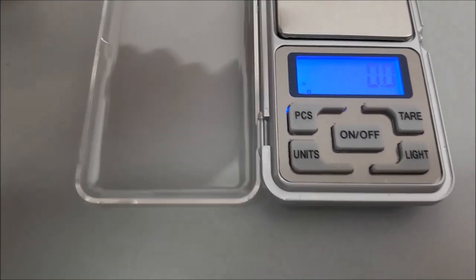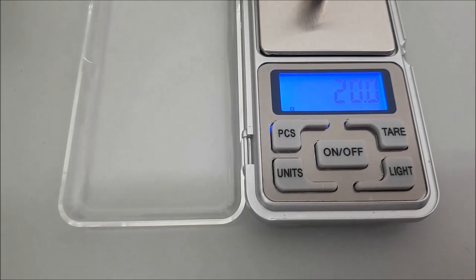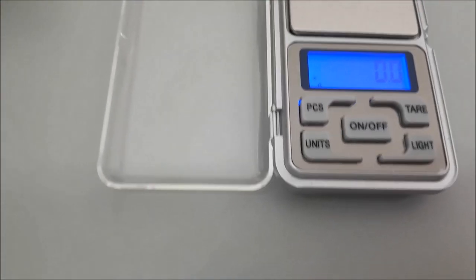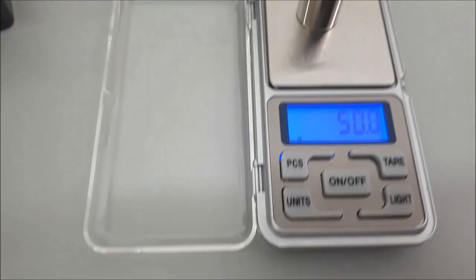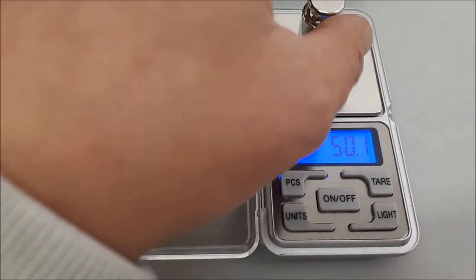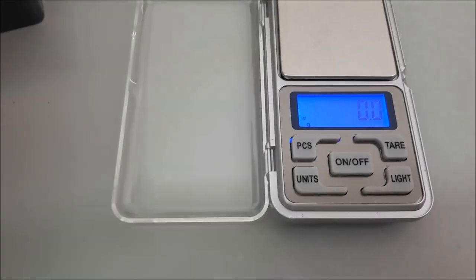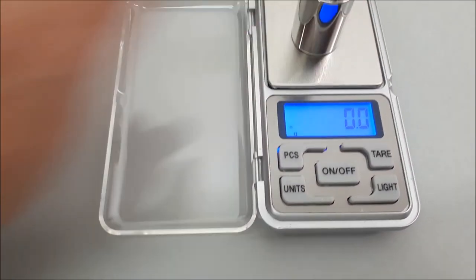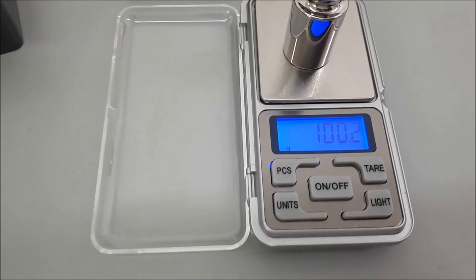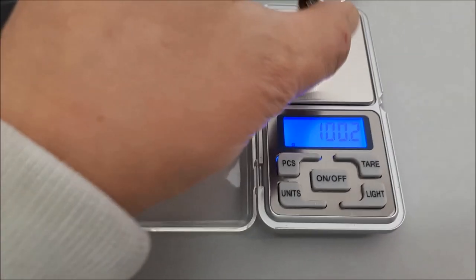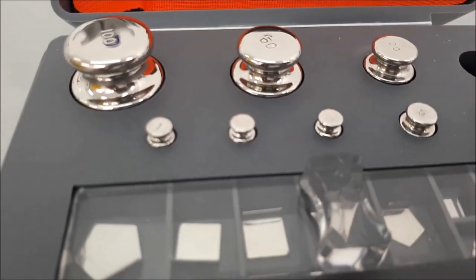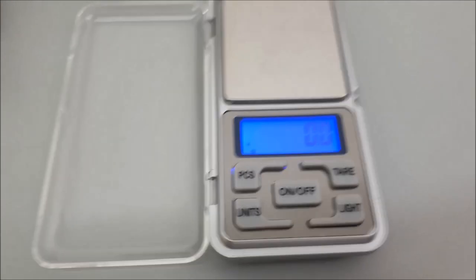20 grams - reads 20.0. 50 grams - reads 50.1, 0.1 gram out. 100 grams - reads 100.2. So all in all, for my needs these are proper accredited weights for calibration, so it's very accurate. It'll do for me.